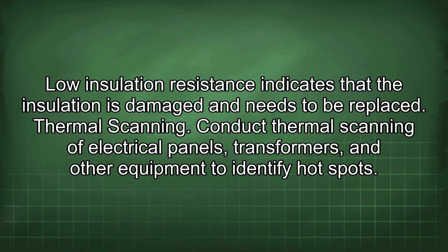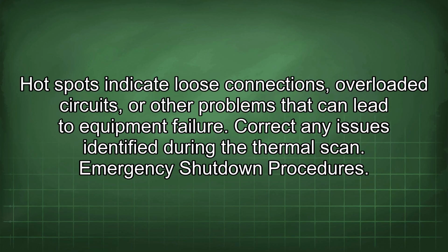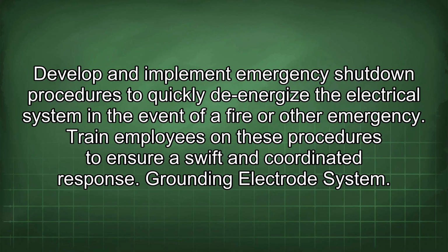Thermal scanning. Conduct thermal scanning of electrical panels, transformers, and other equipment to identify hotspots. Hotspots indicate loose connections, overloaded circuits, or other problems that can lead to equipment failure. Correct any issues identified during the thermal scan. Emergency shutdown procedures. Develop and implement emergency shutdown procedures to quickly de-energize the electrical system in the event of a fire or other emergency. Train employees on these procedures to ensure a swift and coordinated response.